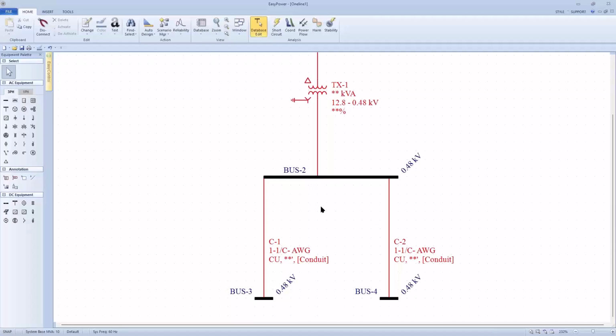The electrician had the responsibility of labeling the above ground distribution system for an oil field there in Oklahoma. He said, "Jim, I've looked at the label on this first cable." I'm going to double click on the cable to open the dialog box. He said, this first cable is a single conductor per phase, so I'm looking at number per phase is 1. The type of cable is a 1C, which means each phase is insulated separately. The type of insulation was THWN because this was an outdoor run. So I need to scroll down a little bit and get THWN. And the size was 350 kcmil. So I'm going to pick out 350.